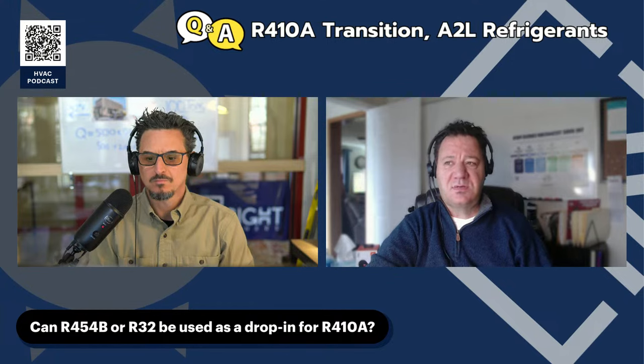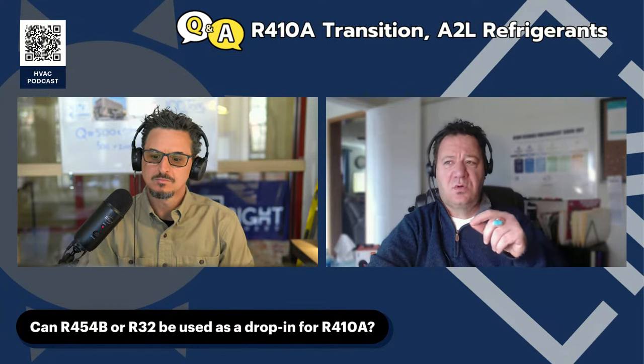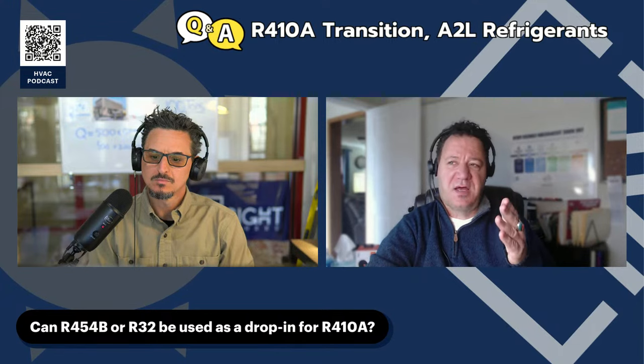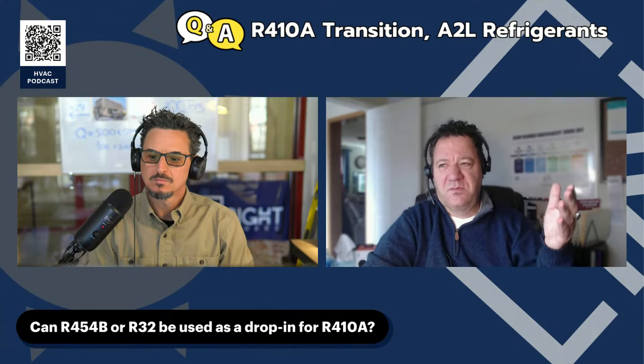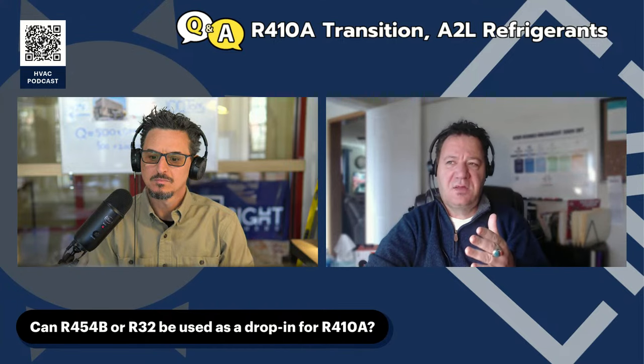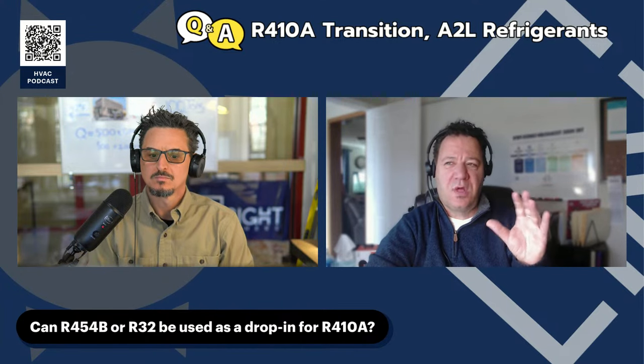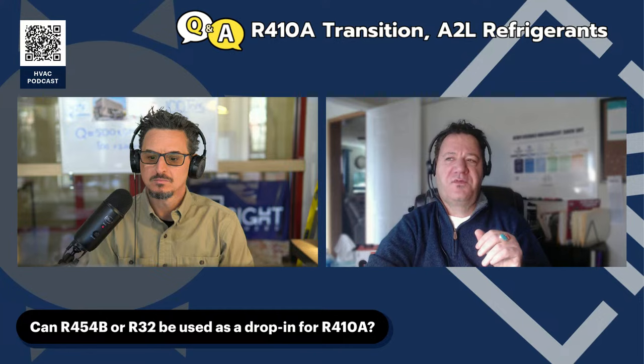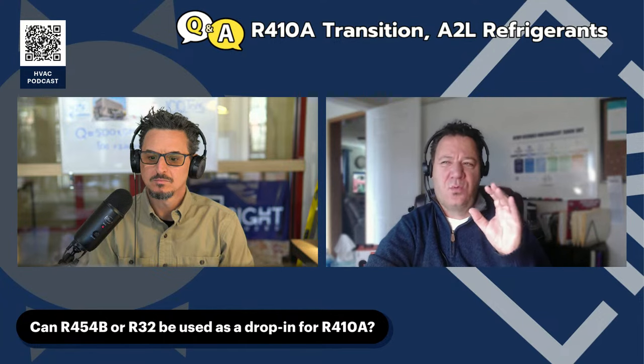But the other thing that wasn't that well known is it keeps that discharge line a little cooler. So if you look at the temperatures, let's say in the same application, 410A on the discharge line will run right around 179. 454B will run right around 190. And R32 will run right around 215 degrees.